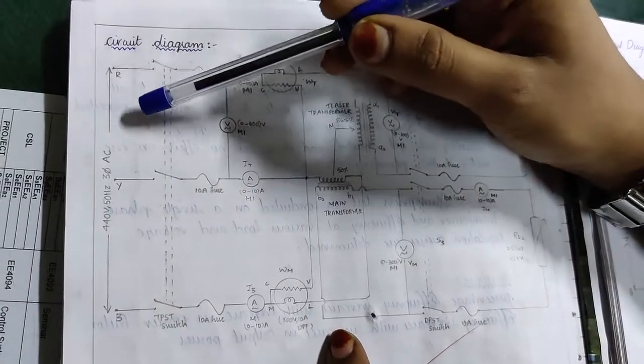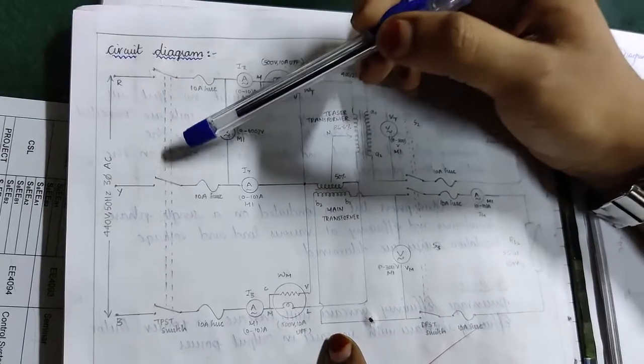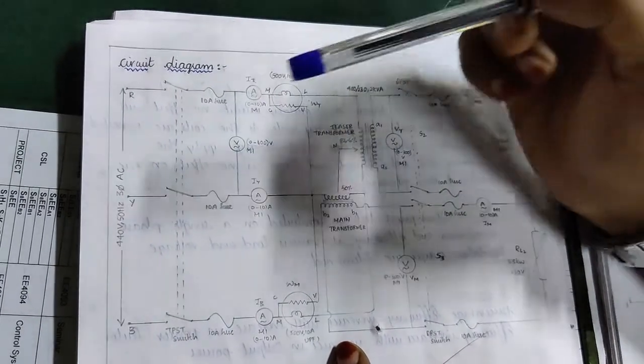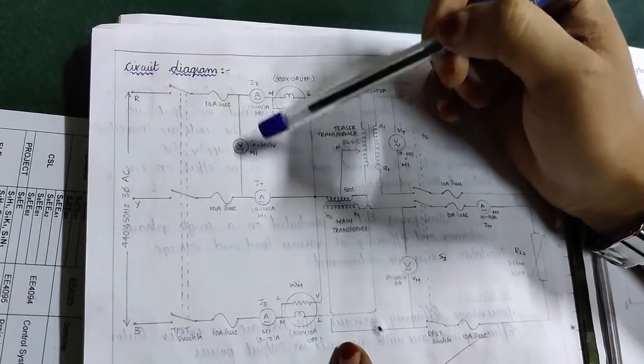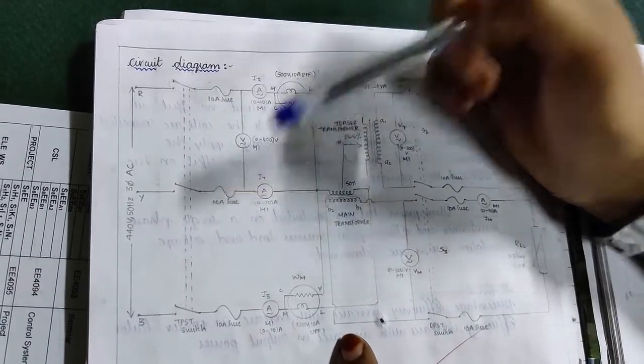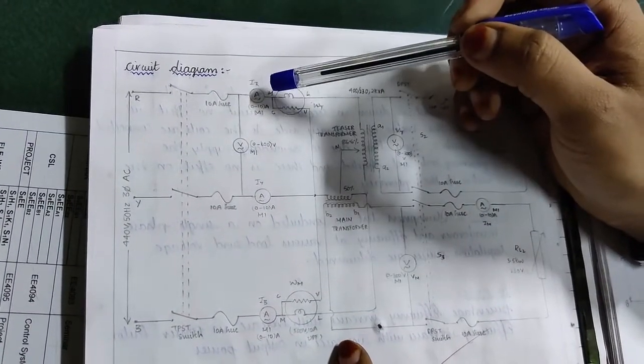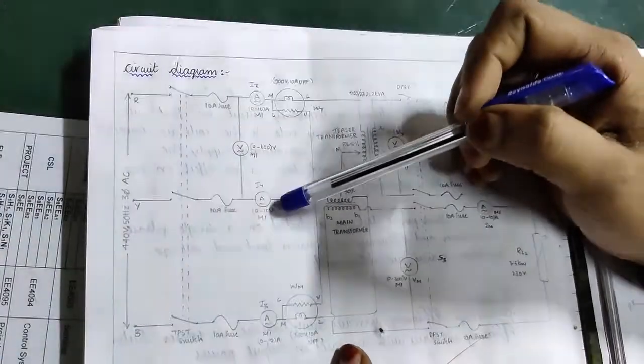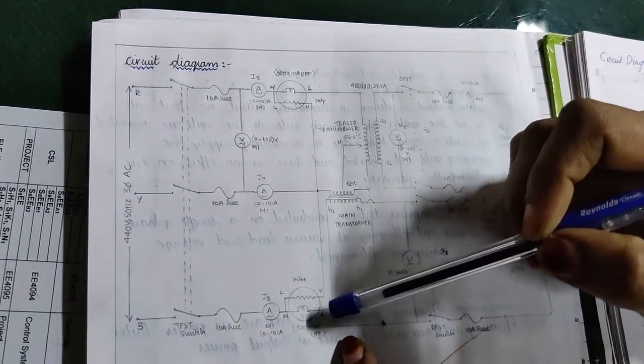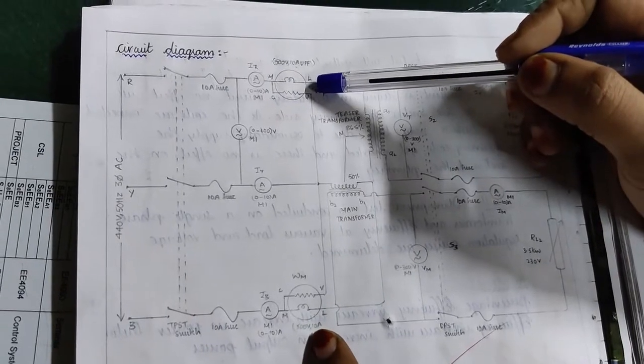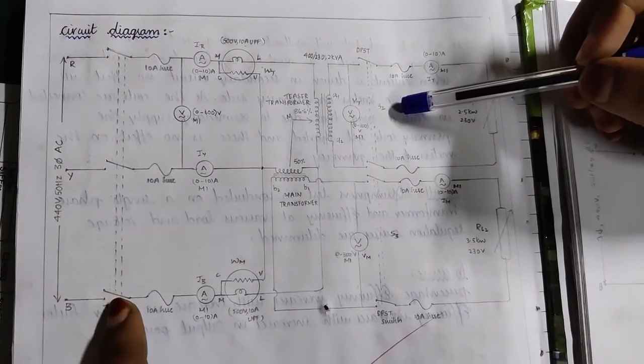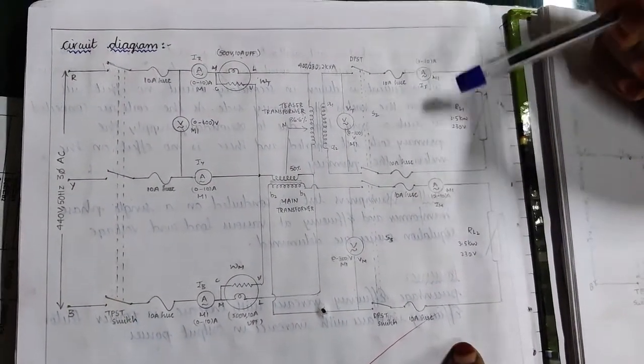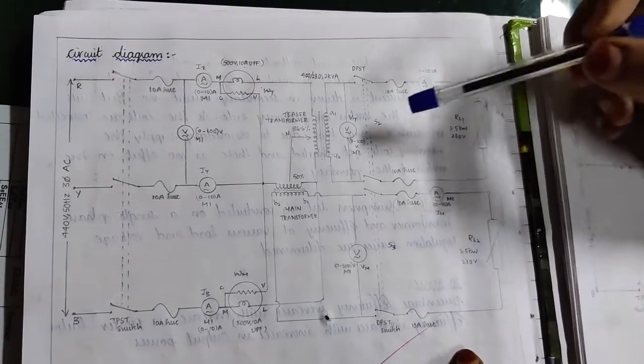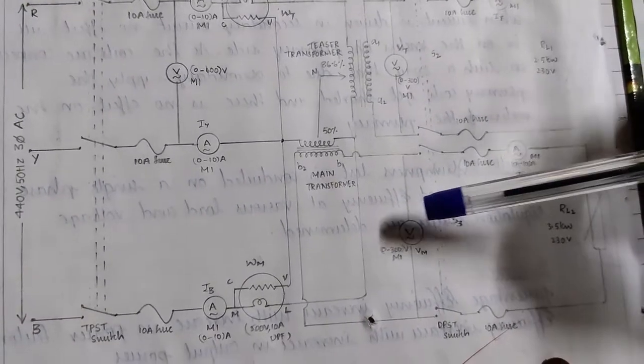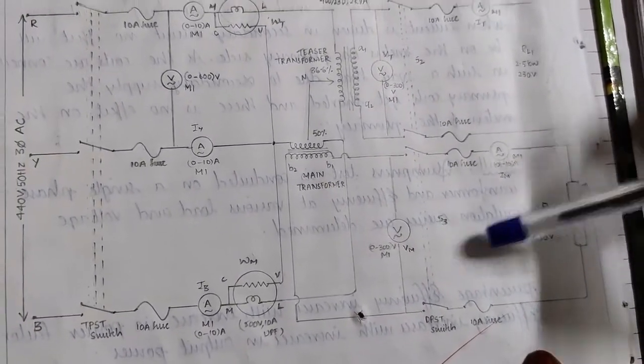From the main three-phase source through auto transformer, we are giving the supply to this circuit. And for measuring the rated voltage, we have a voltmeter across RY. And for the three-phase currents, we have three ammeters IR, IY and IB. And we are measuring the power using 2 wattmeter method. We have the main switch, it is termed as S1, and for the loading purpose we have two switches. For the teaser transformer it is S2, and for the main transformer we have S3 here.